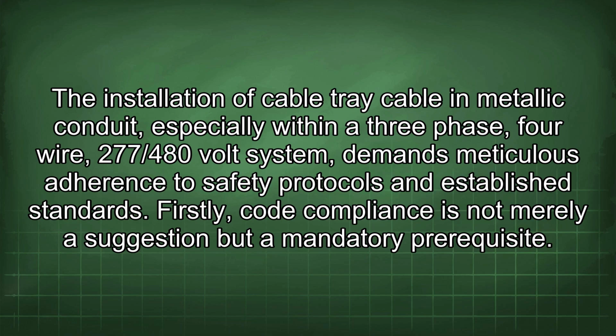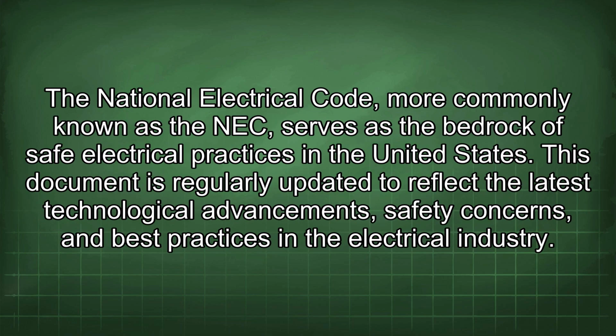The installation of cable tray cable in metallic conduit, especially within a 3-phase 4-wire 277/480 volt system, demands meticulous adherence to safety protocols and established standards. Firstly, code compliance is not merely a suggestion but a mandatory prerequisite. The National Electrical Code, more commonly known as the NEC, serves as the bedrock of safe electrical practices in the United States. This document is regularly updated to reflect the latest technological advancements, safety concerns, and best practices in the electrical industry.